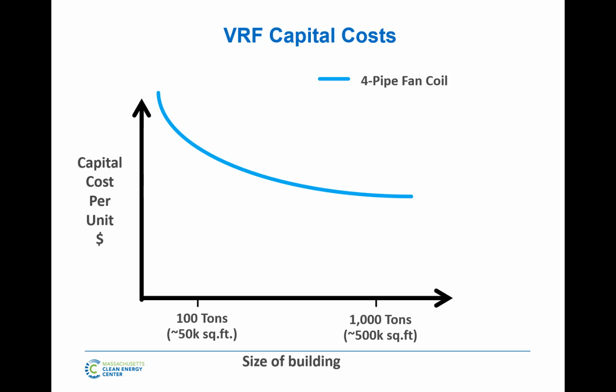So if you have a 4-pipe fan coil, you're buying a boiler, you're buying a chiller, you're buying all the infrastructure that goes with that, the control system. There's a lot of upfront cost, so as you go up in tonnage, as you have more units, as you have more fan coils, your cost per fan coil, your cost per ton is going to actually go down, because you have a lot of upfront costs that don't make sense for a smaller building. Once it gets bigger, you're just adding fan coils, you're not adding more chillers. And similar with a 2-pipe fan coil, same exact curve, not the same exact upfront costs, but same situation, just different costs involved, so it's less expensive.